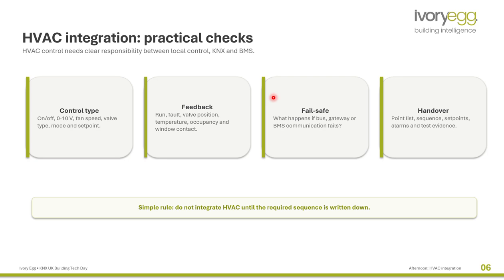Another thing is HVAC integration. This makes your project also complex. Why? Because we have different types of HVAC in rooms and in plant rooms. If we are in rooms, what are we going to control? Is it heating, underfloor heating, radiator, fan coil? Which type of fan coil do we want to control? Is it 3-speed fan or 0 to 10 volt fan?